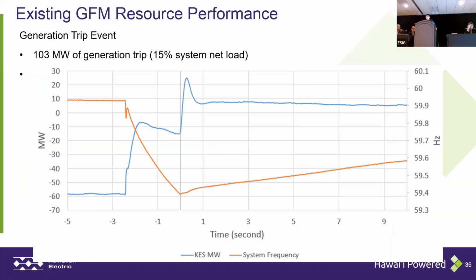This is the first event. I think you may have seen this plot several times. This is a generation tripping event. Around 15% of the system net load got tripped from the tripping of one synchronous machine. In this plot, the blue curve is our KES facility response to this event. I think at that time, this is the only grid forming project online. And then the brown curve is the system frequency.